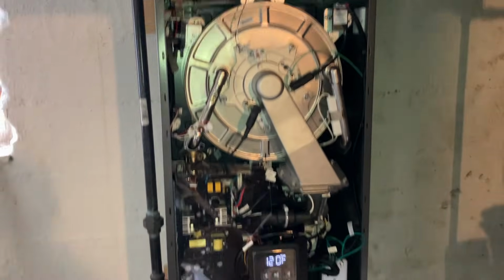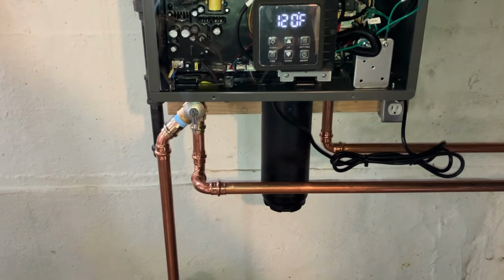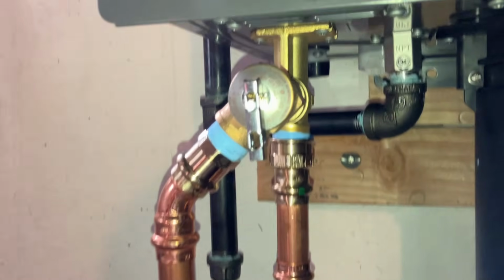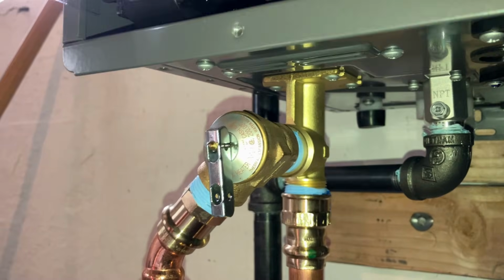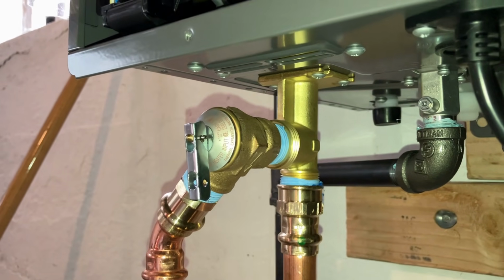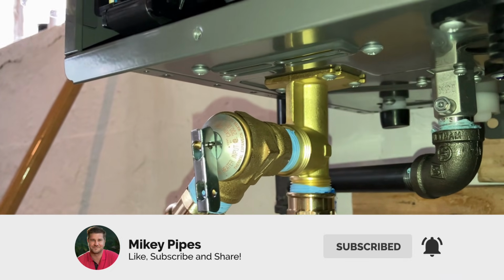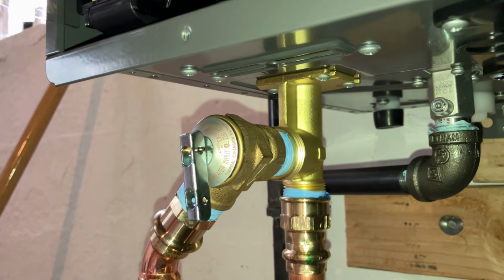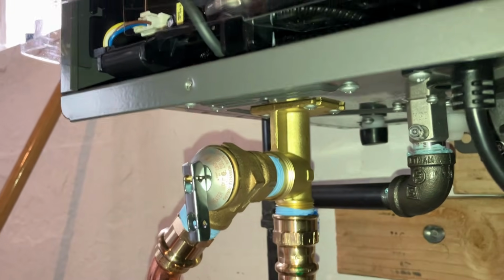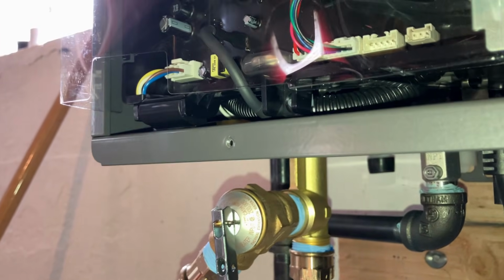Excellent. Look at this. Let's go over this real fast. All right, let's start at the bottom. We have our temperature and pressure relief valve. It connects right there to that factory installed connection. You'll take the cap off, and there's outside threads and inside threads. You'll screw in the included temperature and pressure relief valve right on that.